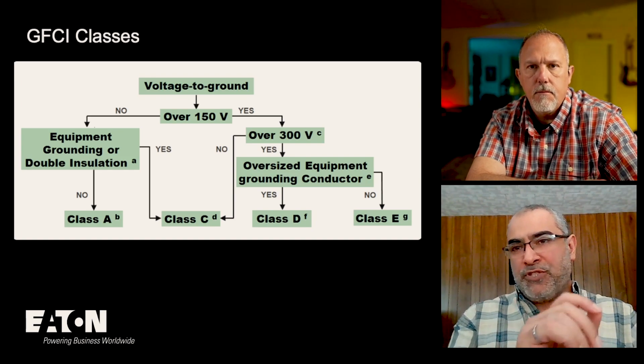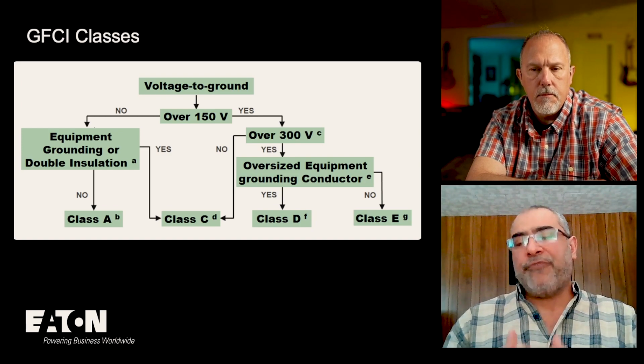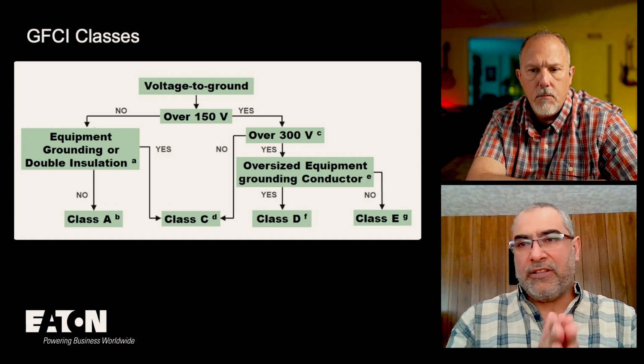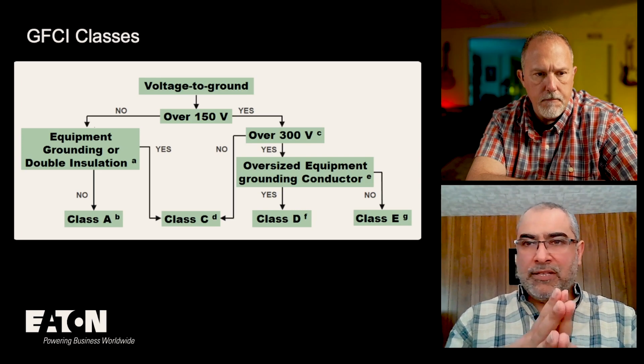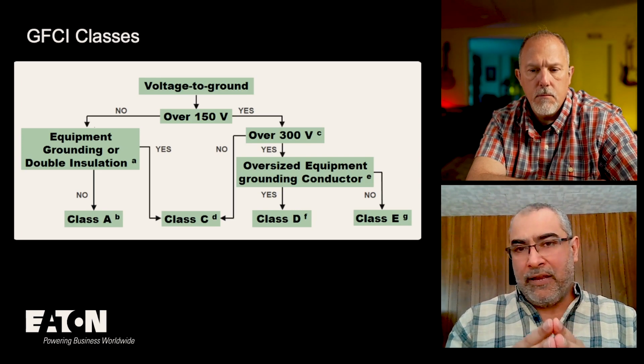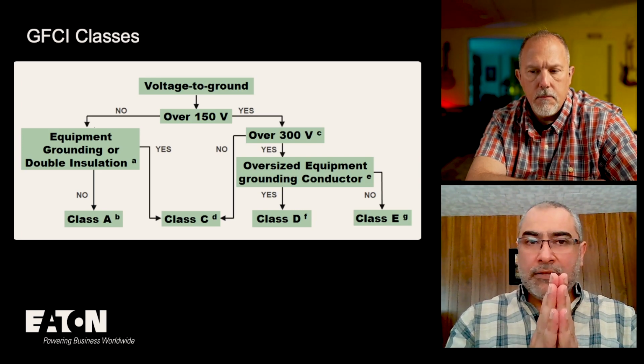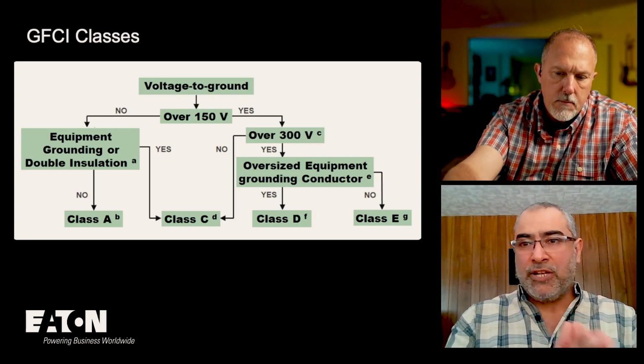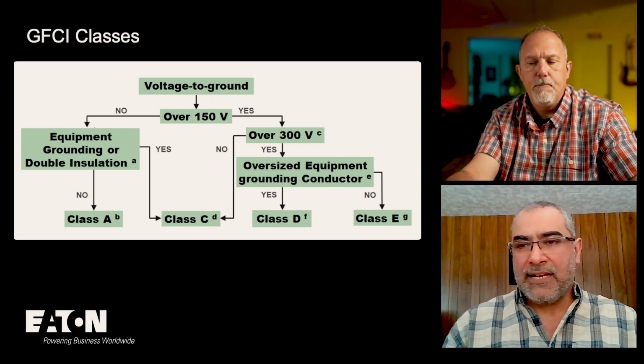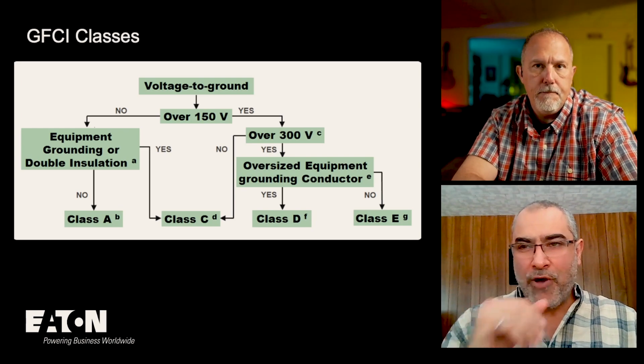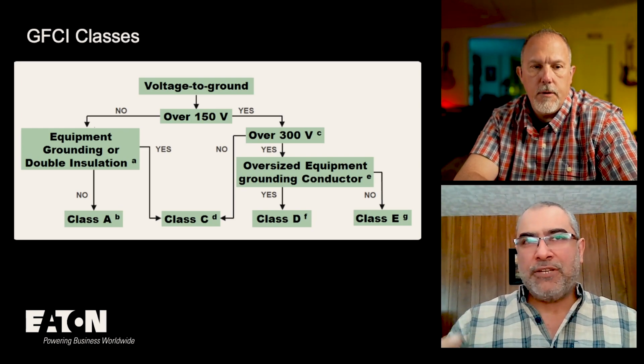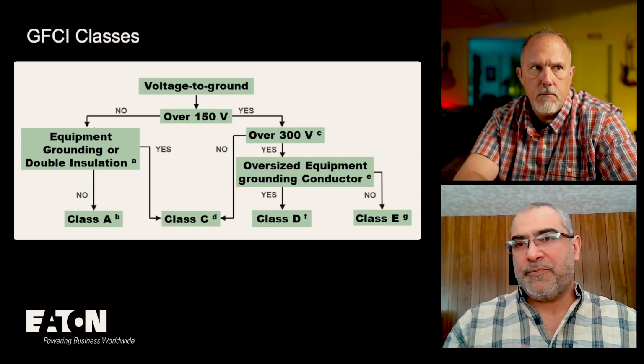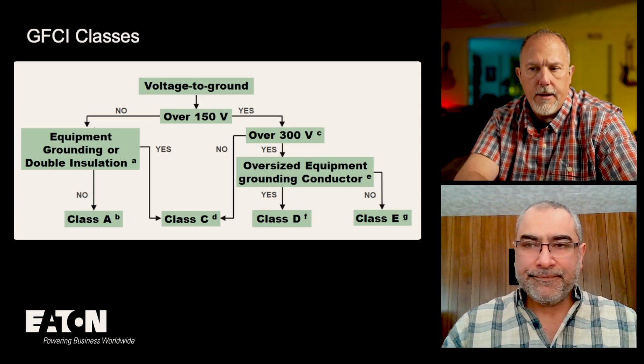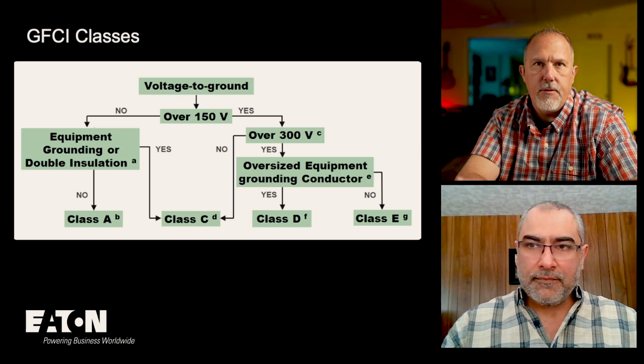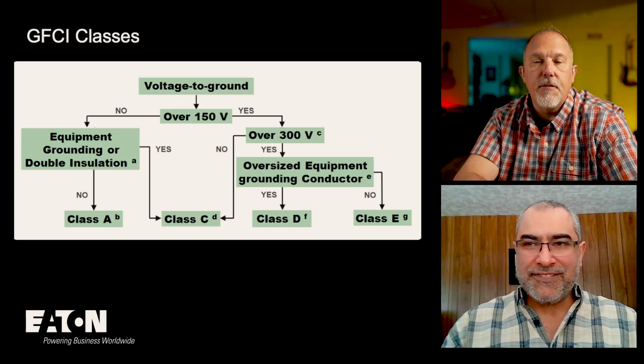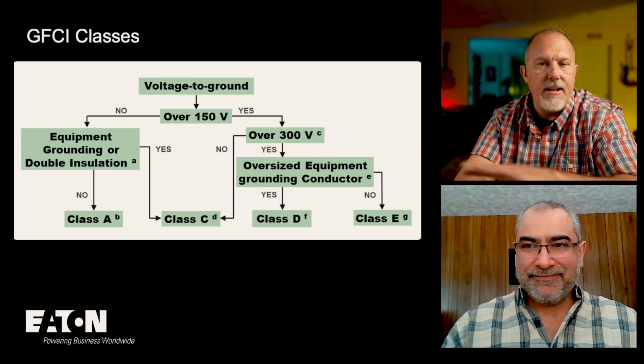So my point with special purpose GFCIs is that it's nothing different, it's a product required by the NEC and installed widely, but the UL document is just an outline of investigation, not a standard. I brought up AFCI as an analogy because AFCIs are more popular than special purpose GFCIs. I just want to make sure nobody mistakes an AFCI for having anything to do with GFCI protection.